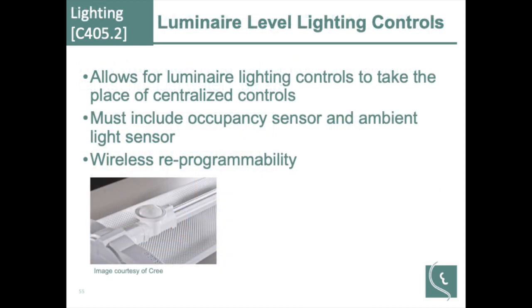Lighting levels. C405.2 allows for lighting controls to take the place of centralized controls. Instead of having timers on systems or a central automation system to independently control your lighting, lighting can have built-in occupancy sensors on each fixture. You also must include an occupancy sensor and an ambient light sensor and wireless reprogrammability so that these things can be set up independently.